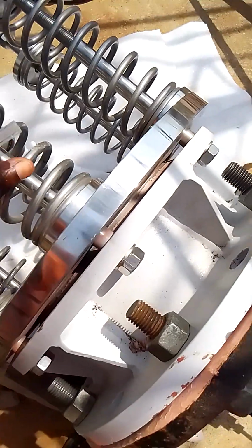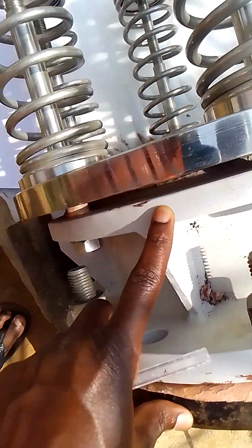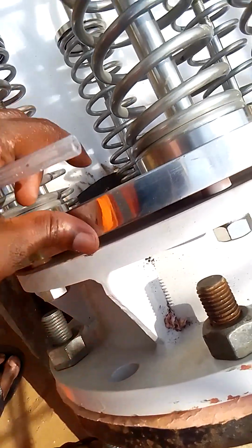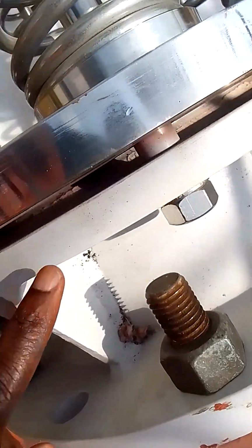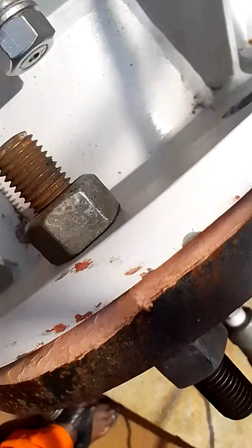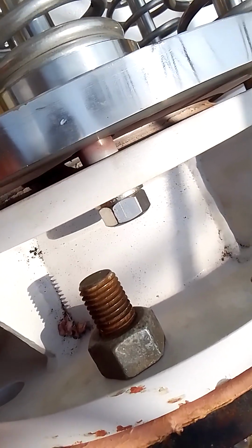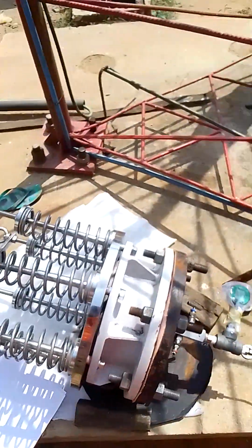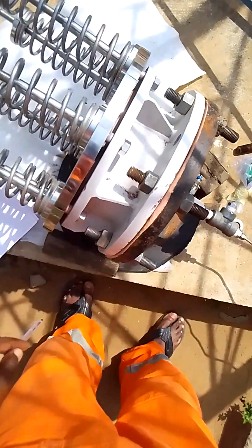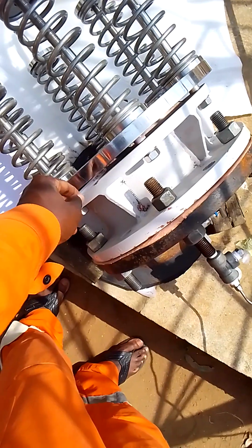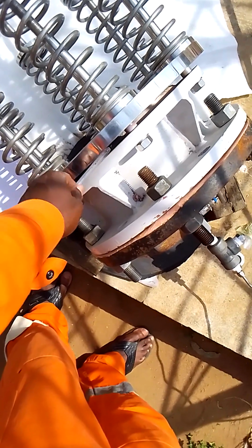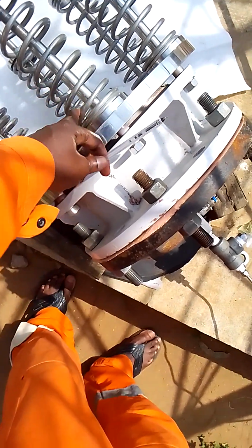What I also want you to know is that there's a separation between this valve and this actuator. This place I'm touching now is where the vent will come from. When the pressure approximates the set point of this valve, it will pop up. This place will pop to release the air. Once it pops, it pushes this actuator part up.